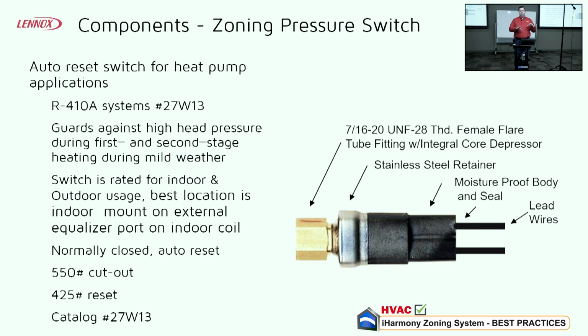This is not here to protect the compressor in the same way that the pressure switch in your heat pump is. The onboard pressure switch that has a 5-strike lockout in your outdoor unit cuts out at just below 600 PSI, maybe 595, somewhere in there. When that trips 5 times in a row, or 3 times or 5 times, I'd have to look at the spec, it's going to lock out. So if that happens, the heat pump's gone, and you're going straight to electric heat. That gets a whole lot more expensive in a lot of scenarios.